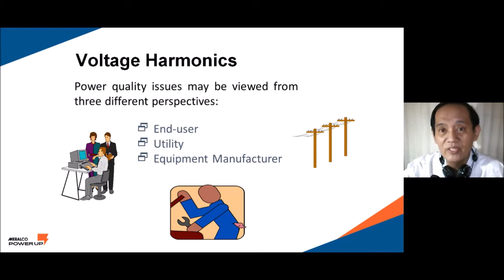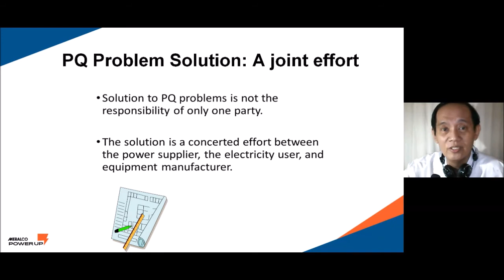Even though Meralco provides a stable 230 volt supply, if the equipment manufacturer's equipment is designed for a 50 hertz supply based on 220 volts, you're going to have a very big problem operating that equipment. So it is always going to be a joint effort to ensure good power quality.